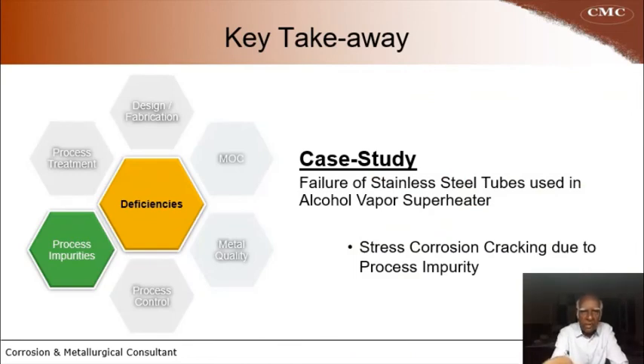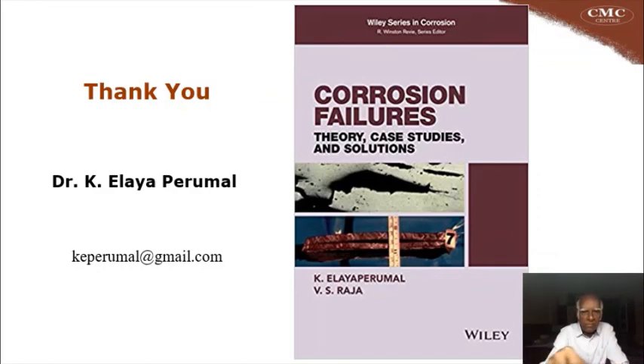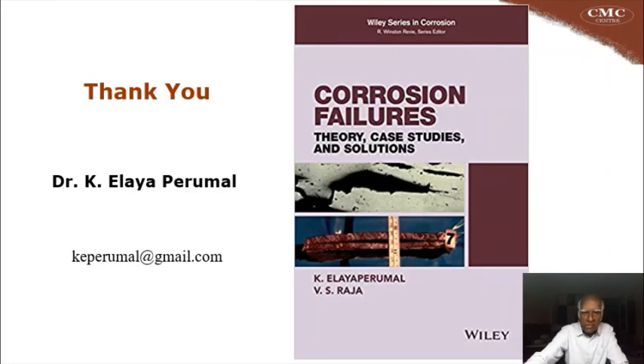The key takeaway from this case study is that we have seen the premature failure of stainless steel tubes used in an alcohol vapor superheater. This category of failure belongs to the reason of impurity in the process medium — stress corrosion cracking due to process impurity. Thank you very much. The book written by me and Professor V.S. Raja of IIT Mumbai will give you details of corrosion theory and several failure cases.